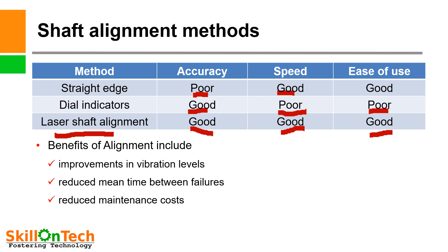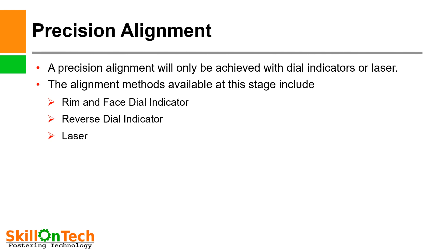Benefits of alignment include improvement in vibration levels, reduced mean time between failures, and reduced maintenance cost. Your alarms with laser shaft alignment will drastically reduce. If your alignment is perfect, then you will find the results of good alignment. Precision alignment will be achieved with dial indicators or laser indicators. The alignment methods available include rim and face dial indicator method, reverse dial indicator method, and laser alignment method.